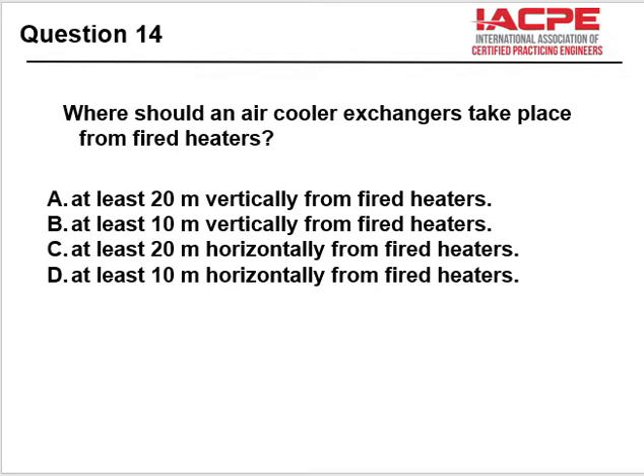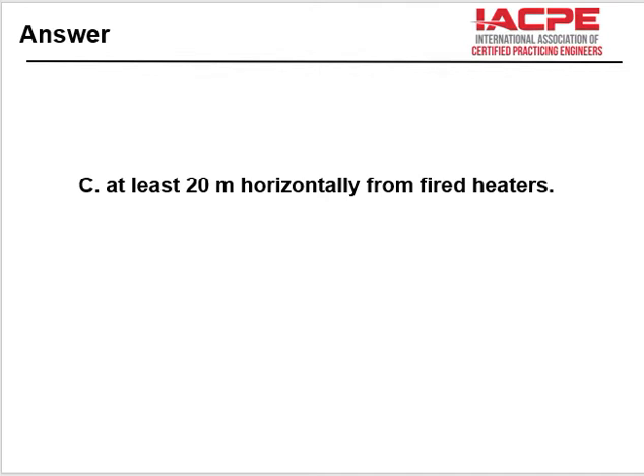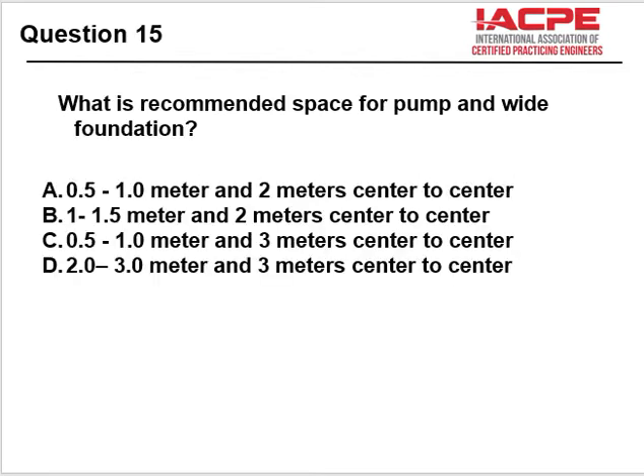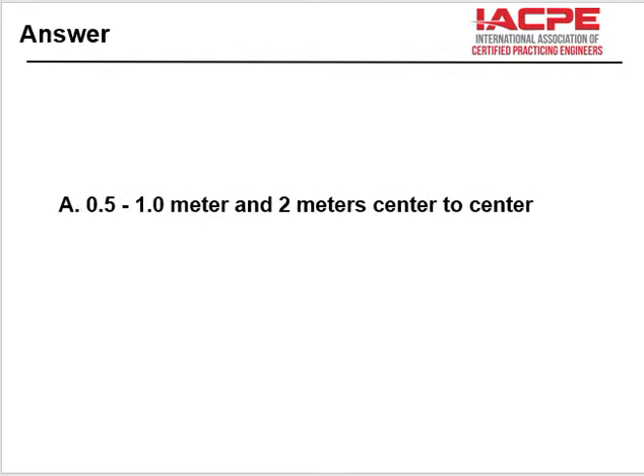Where should an air-cooled exchanger be placed from fired heaters? So, how far away should an air-cooled heat exchanger be from a fired heater? At least 20 meters horizontally. What is the recommended space for pump and wide foundations? 0.5 meter to 1 meter and 2 meters center to center.